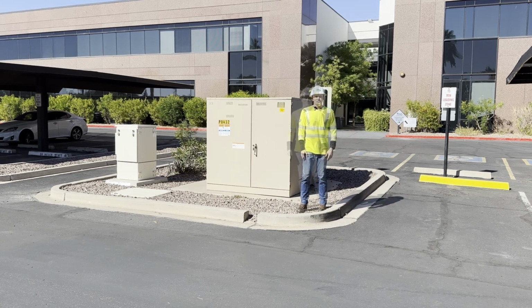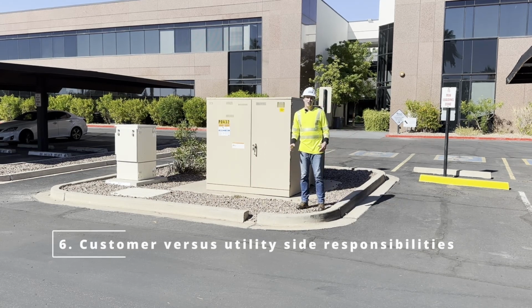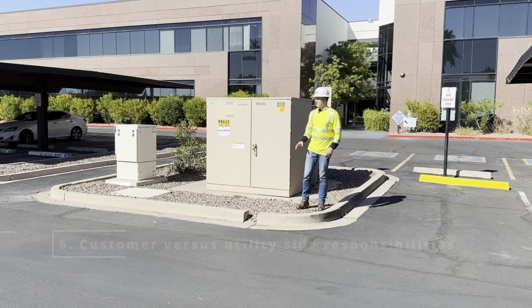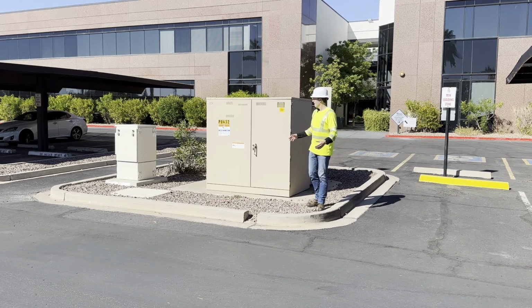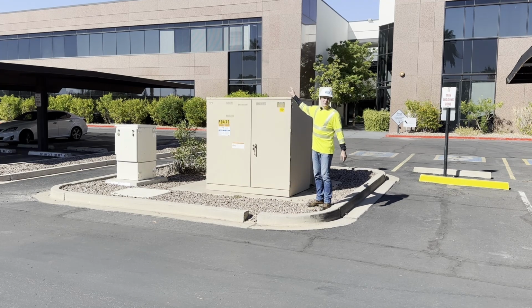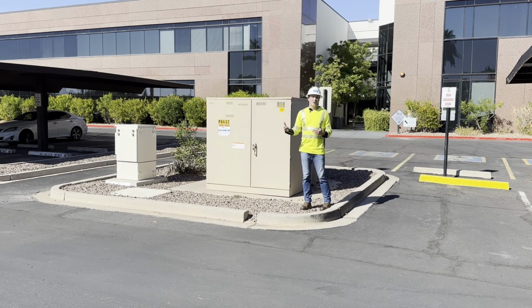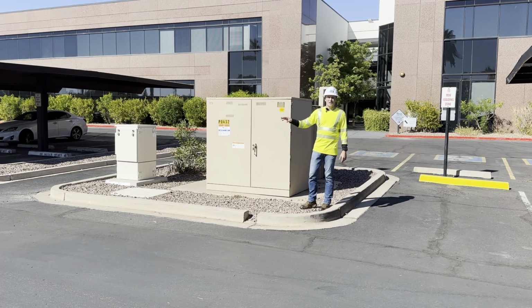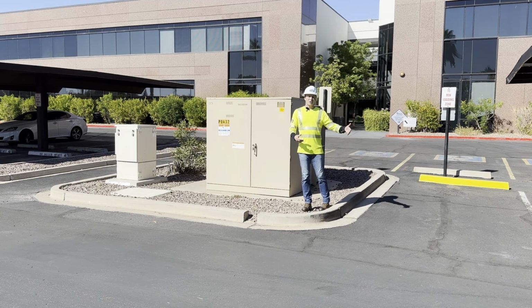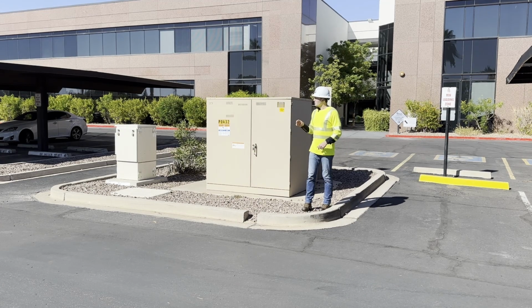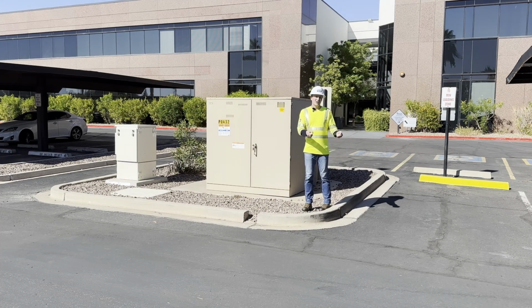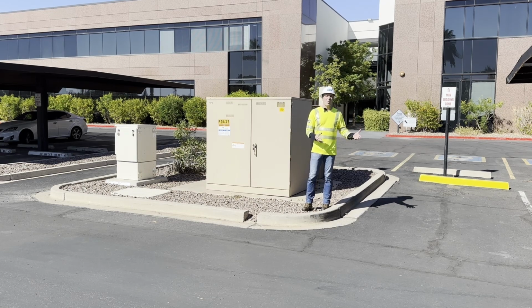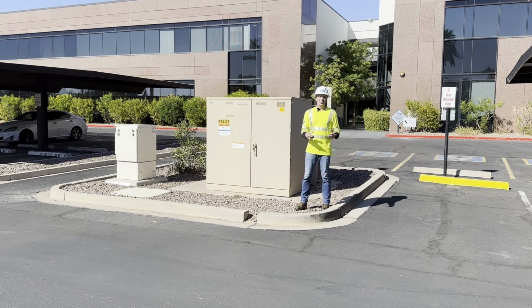Number 6, we're going to talk about customer versus utility side responsibilities for siting these transformers. It might look like this transformer is owned by the building behind us, but in reality, it's always going to be owned by the utility for secondary services. It's important that you work with your utility when it comes to developing your project from the get-go, because there are going to be certain responsibilities for you as the customer developing this project, and certain responsibilities that the utility has, and that's all laid out in the ESRs, the electric service requirements for each utility. And unfortunately, they're all different.